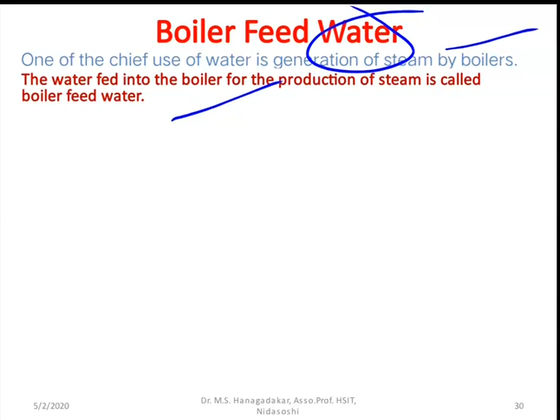If the water has to be used in the boiler, there are certain conditions on its quality. If these conditions are not fulfilled, then operation of the boiler becomes intolerable. Hence, the boiler may lose its efficiency. Now let us discuss the essential requirements of boiler feed water. The water should be free from the following parameters. Let us discuss the first one. The water should have zero hardness. It means the hardness of calcium and magnesium should be 0 ppm. If that is not possible, it should be less than 0.2 ppm.